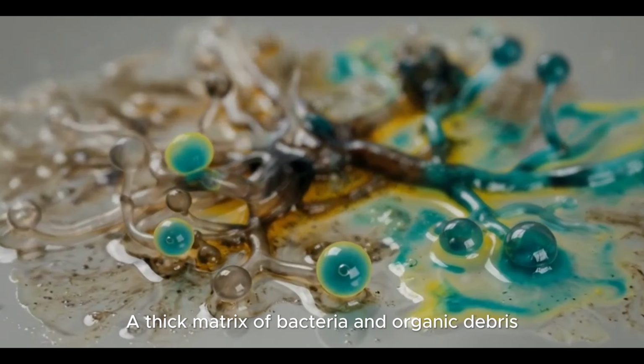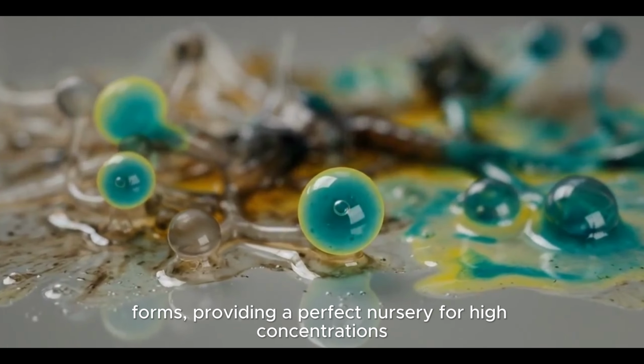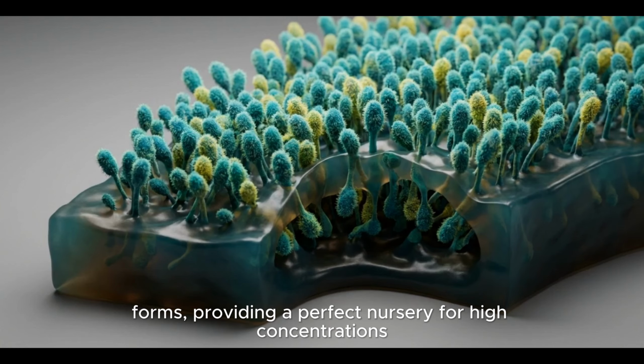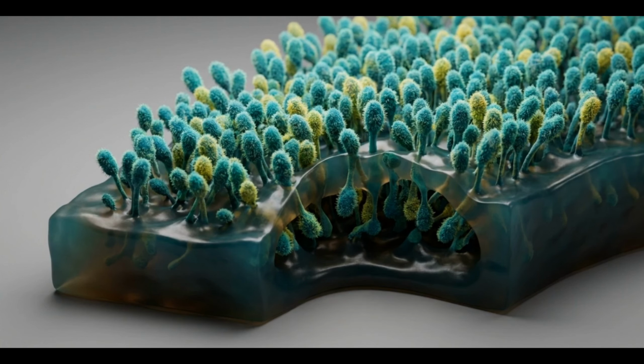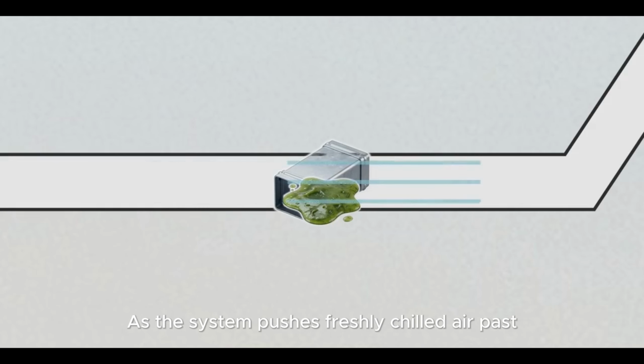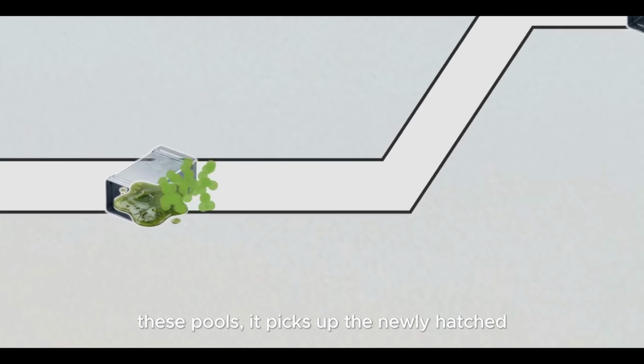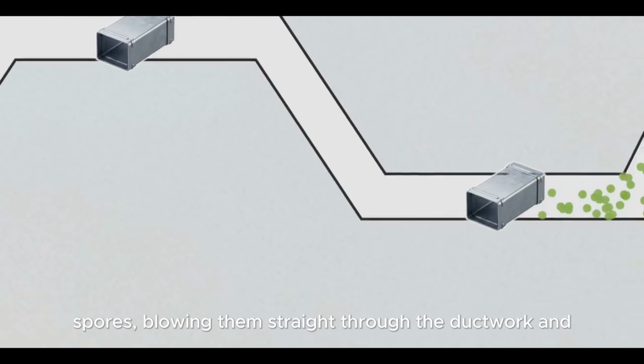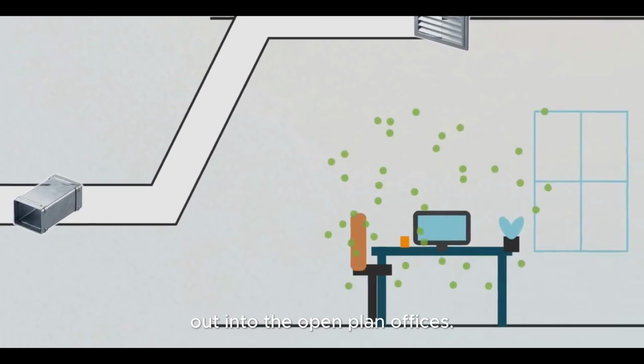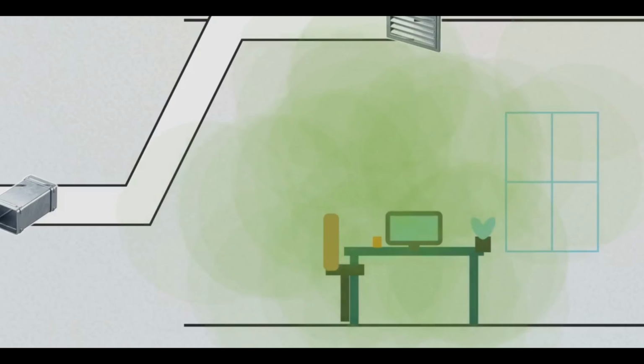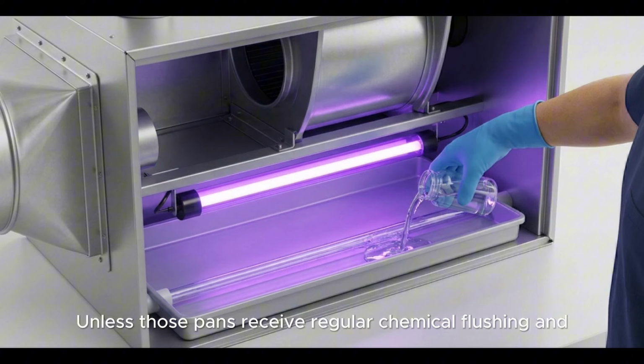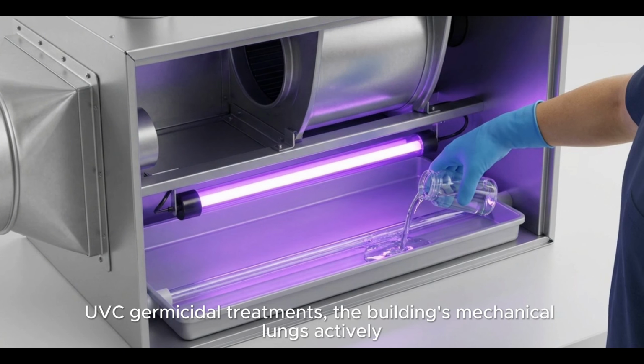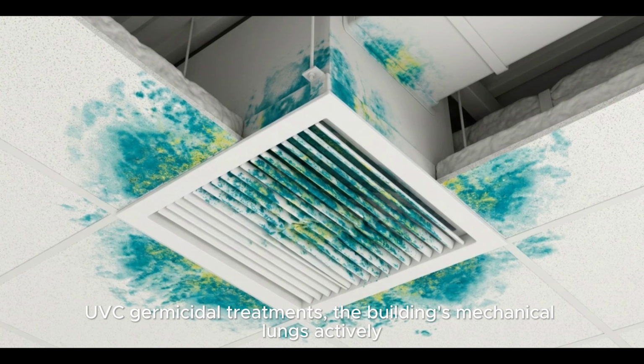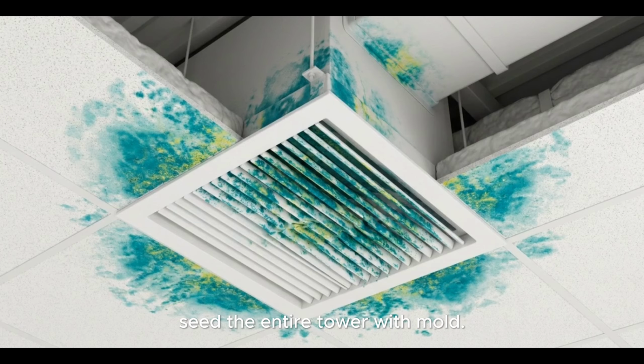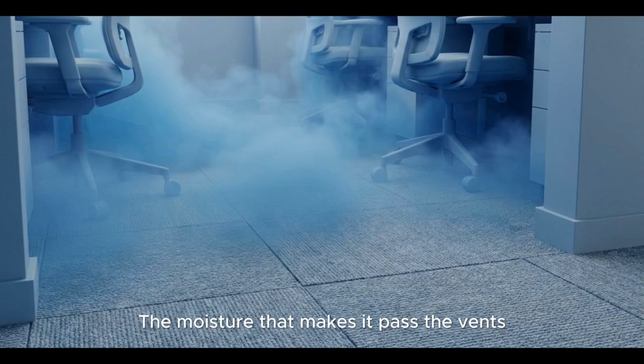A thick matrix of bacteria and organic debris forms, providing a perfect nursery for high concentrations of fungal spores. As the system pushes freshly chilled air past these pools, it picks up the newly hatched spores, blowing them straight through the ductwork and out into the open plan offices. Unless those pans receive regular chemical flushing and UVC germicidal treatments, the building's mechanical lungs actively seed the entire tower with mold.